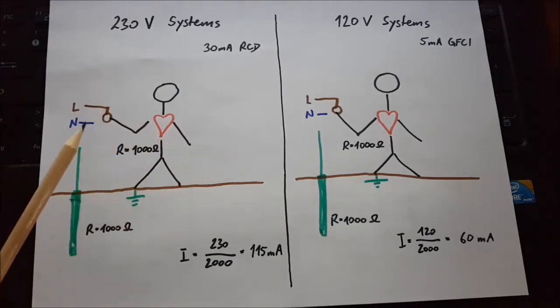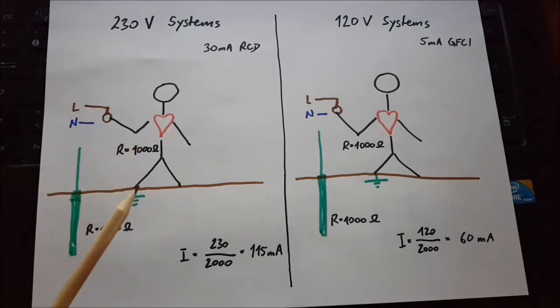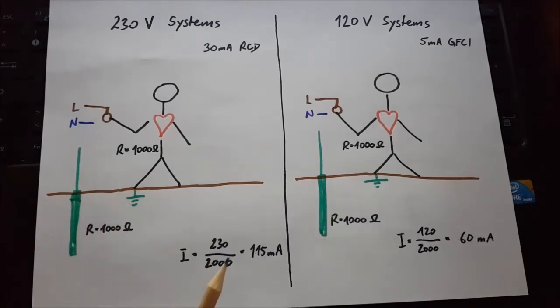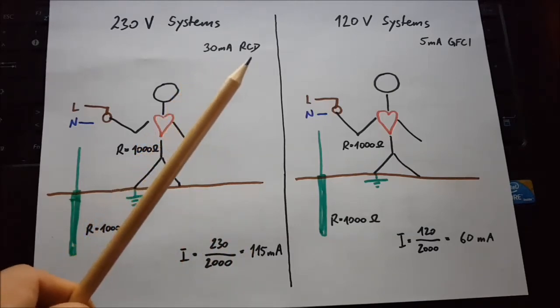The human, if he touches a hot wire with his hand and the current will pass through his foot, normally will have a standard resistance at around 1000 ohms. And then we have a second resistance. In this case, it is called the impedance of the grounding earthing system. So let's say that one is as well 1000 ohms. We have a total resistance here of 2000 ohms. If we now divide the voltage through 2000, then we will see if the human is causing a ground leakage, it will cause a 115 milliamp leakage in that system. So 115 milliamp, which will actually be caused against 30 milliamp RCD.